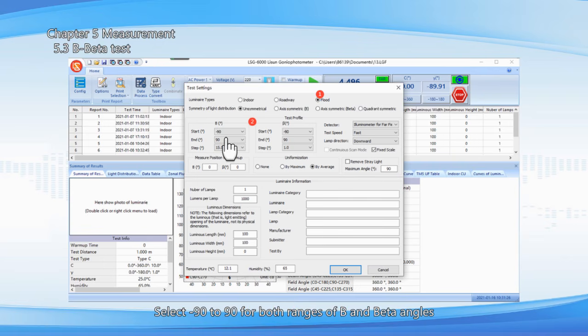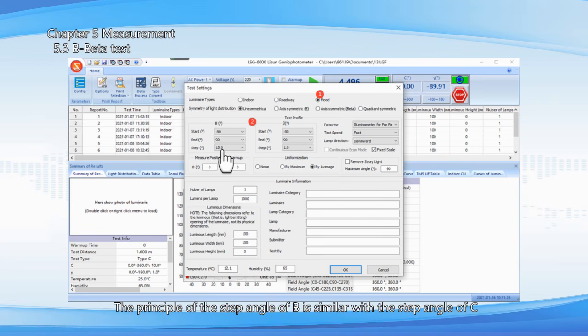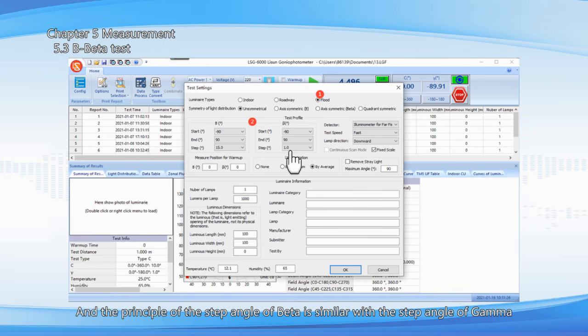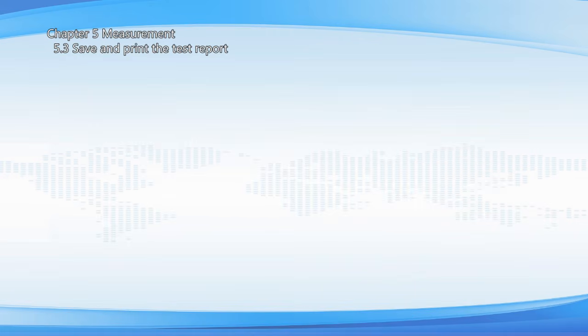Select -90 to 90 for both ranges of the B and beta angles. The principle of the step angle of B is similar to the step angle of C. And the principle of the step angle of beta is similar to the step angle of gamma. All the other settings are the same as the C-gamma test. There is no standard that asks you to do a color distribution test for B-beta. So you can't do a color distribution test after the B-beta test.